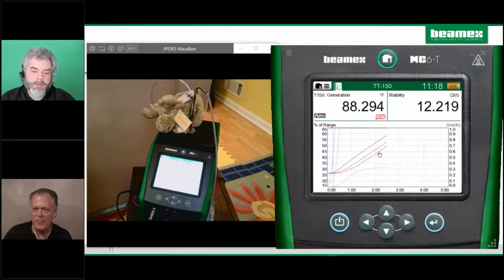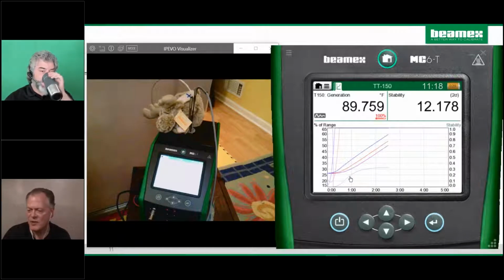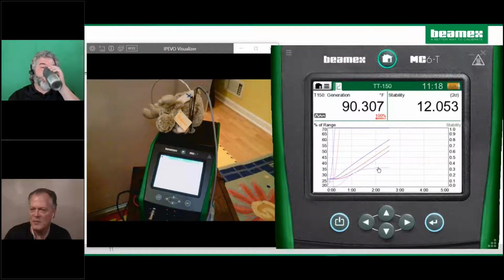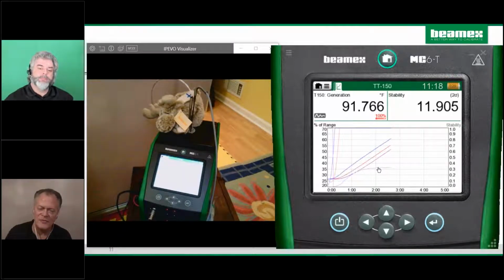Right. So one of the things, I already had it set at 40 degrees, but it would have taken around 10 minutes to get from 72 degrees in my office down to 40. Okay. If we had tried to go to 0, it would maybe take 15 or 20 minutes. So we really are saving at least 20 minutes of field time by just doing this 2-point test.